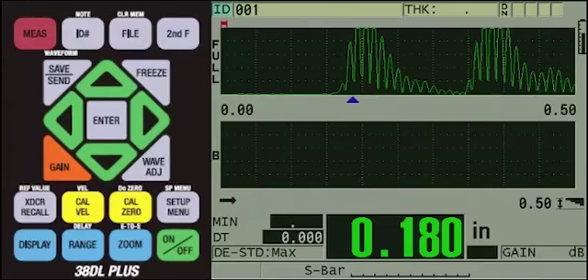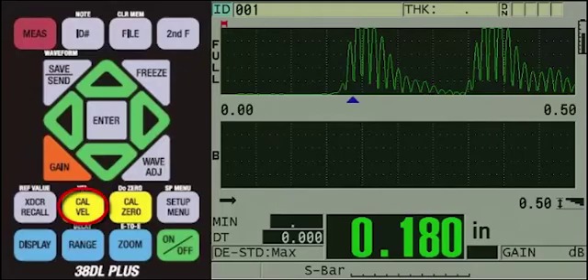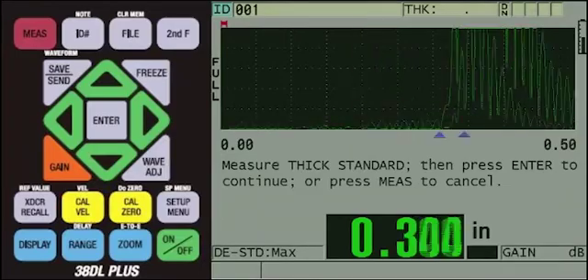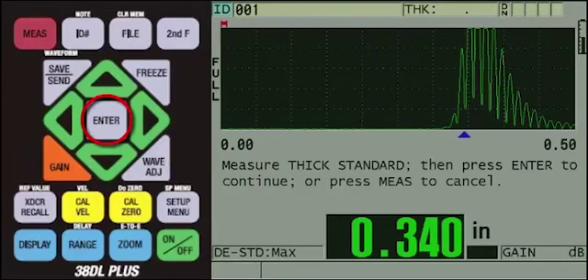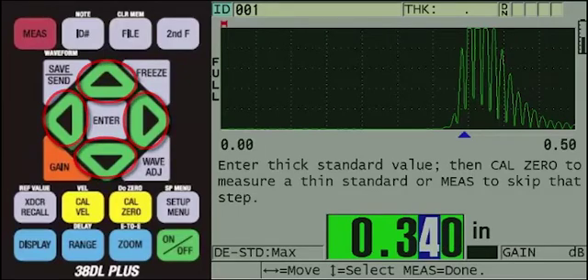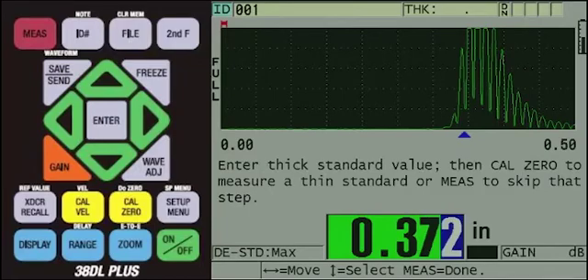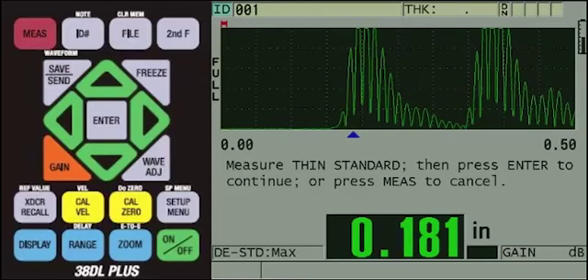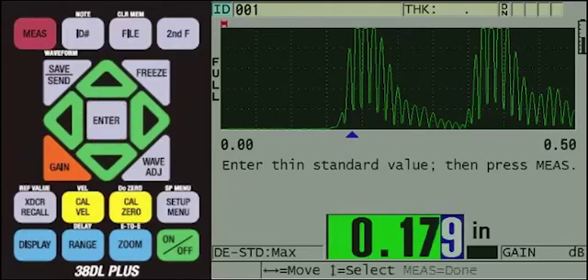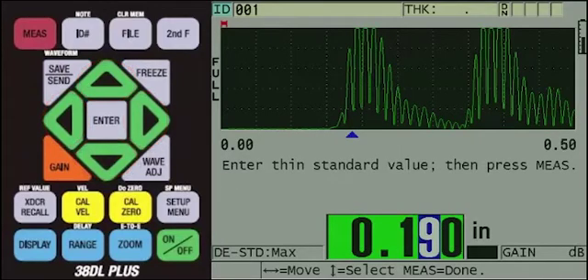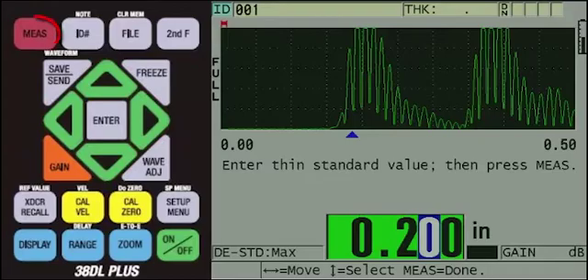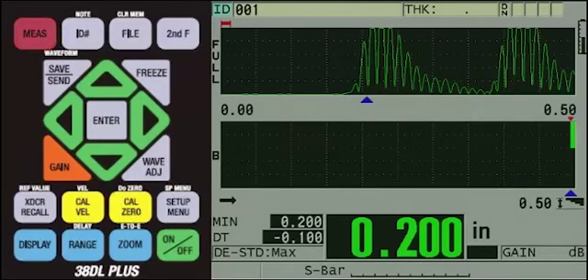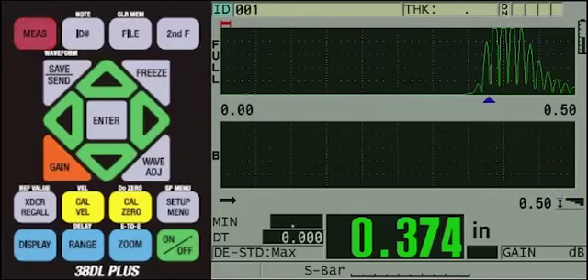Before we perform the scan, we will calibrate the instrument using the 0.375 inch, or 9.53 millimeter thick area of the plate, and the 0.200 inch, or 5.08 millimeter thin area of the plate. To do this, we will first press the yellow Cal Vel key. Then, we will position the buggy over the thick area of the aluminum plate. Once the reading is steady, press the Enter key. Then we will use the arrow keys to change the value to 0.375 inches, or 9.53 millimeters.